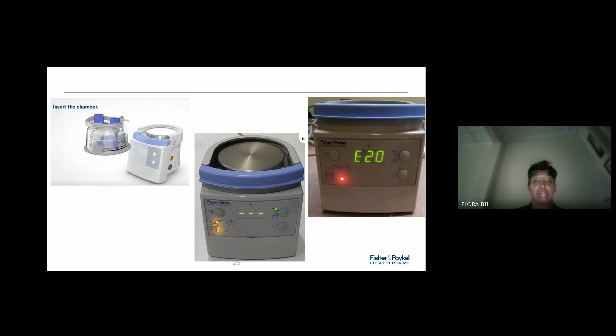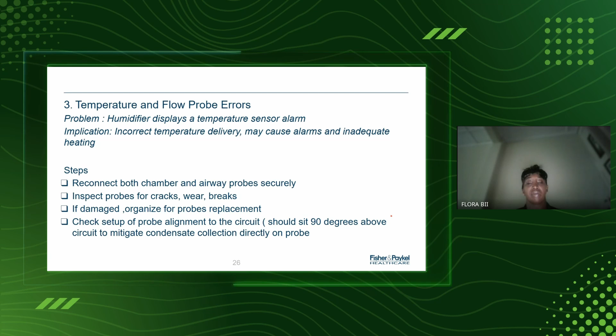Temperature and flow probe errors are also a common one, where you'd find temperature sensor alarms. The steps would be to reconnect the chamber and inspect the probes once again, and check the probe alignment as well. For the probe alignment, I will show you how it should sit. It should sit 90 degrees above the circuit itself so that it doesn't collect mobile condensate and relay wrong information to the humidifier, which might then, because of its algorithm, change certain parameters.